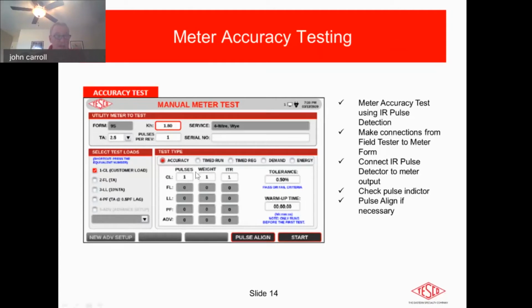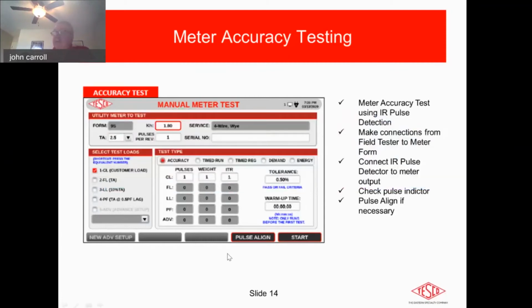You choose exactly how many pulses. In this case, with one, you choose a weighted average. Because it's one, there wouldn't be a weighted average, but it's useful if you decide to do maybe 8 pulses, 10 pulses. That will really be determined by how much load is on that meter and how fast it may be rotating, or not rotating in today's world, but how many revolutions, how many pulses we are likely to see. It can take some time, so it's a decision really at the time when you set this up. One pulse would give you the answer. There's no doubt about it. You should have the accuracy you need with one pulse.